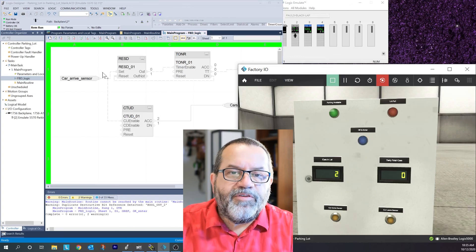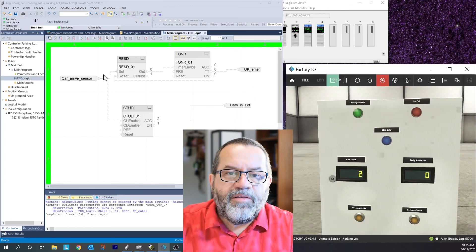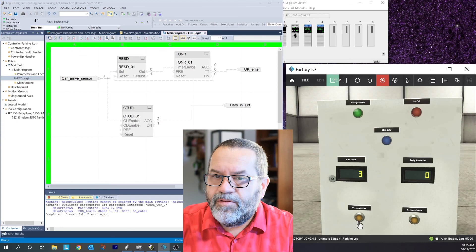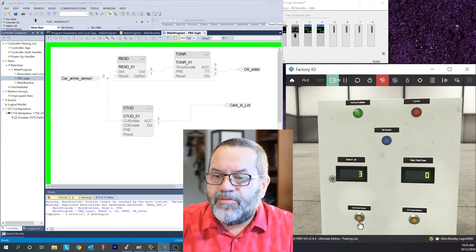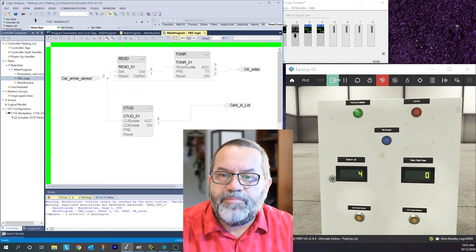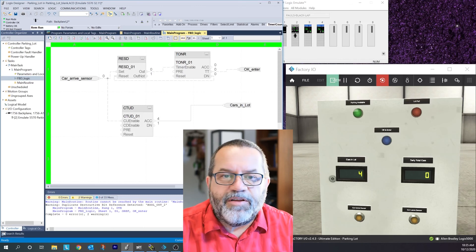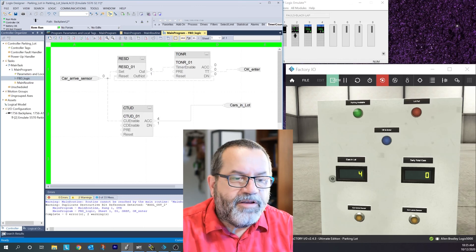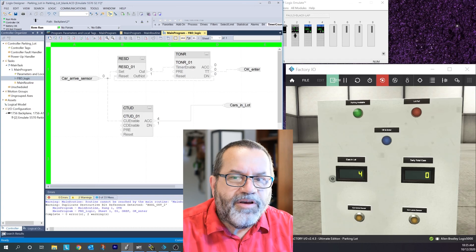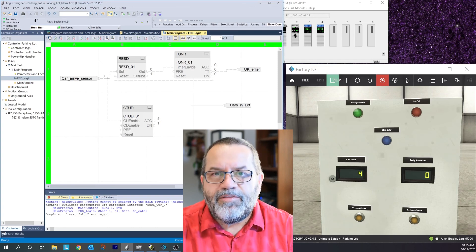It's working - my car arrive sensor goes hot. It doesn't turn green, it just shows with an update that the value went from 0 to 1. While my timer is accumulating, timer timing lights the blue light - and it's doing it. However, it seems to be going on and resetting, so I think it's being affected by that main routine. That's fine - I can go back and fix that. That's what PLC programming is all about: you set up your routine, go online, test it, see what's not working, and go back offline to fix it.